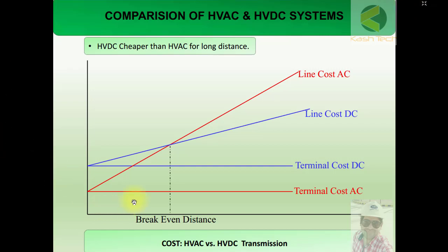Another thing that needs to be considered is the HVDC transmission line versus HVAC related to cost. Here you can see the line cost of AC is shown in red color, whereas the line cost of DC is shown in blue color. So for a shorter transmission line, the AC transmission line is less costly.